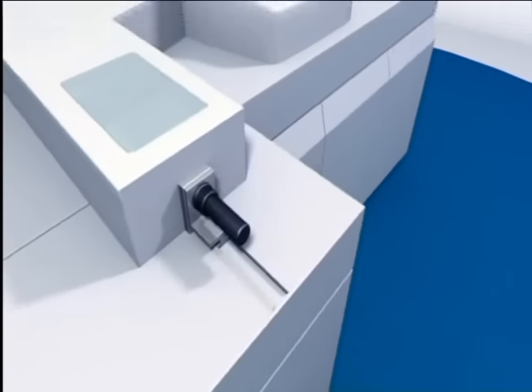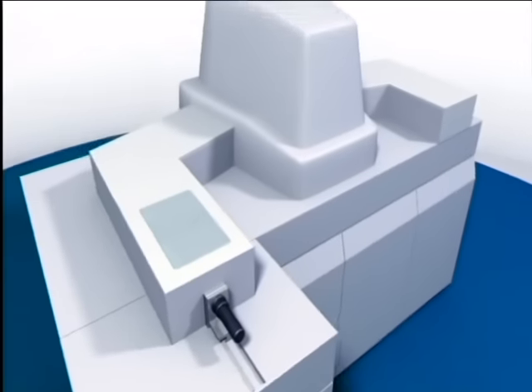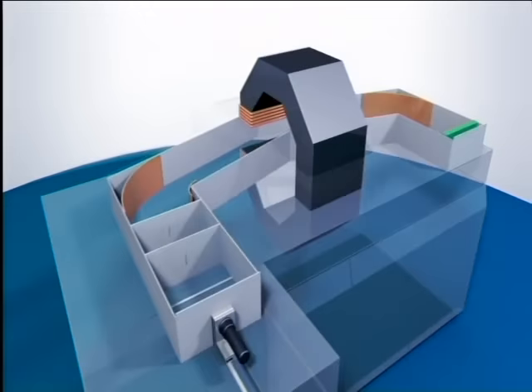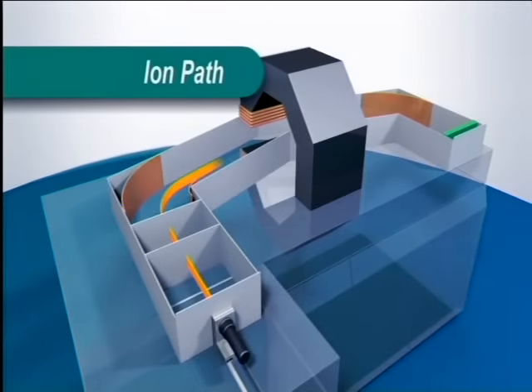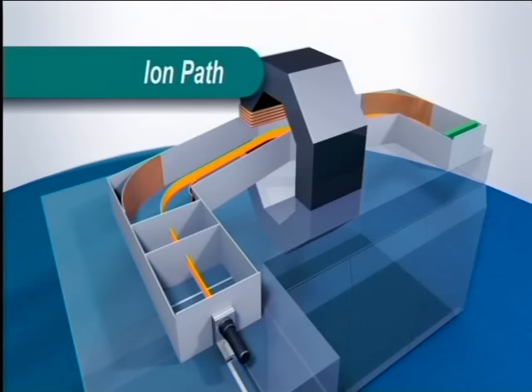The positive ion beam passes between two charged curved plates, which deflect it in a curve so that it enters the area here, where an electromagnet produces a vertical magnetic field. This further deflects the beam in an arc of a circle. On emerging from the magnetic field, the beam is deflected again by another set of charged plates, which direct it into the detector.